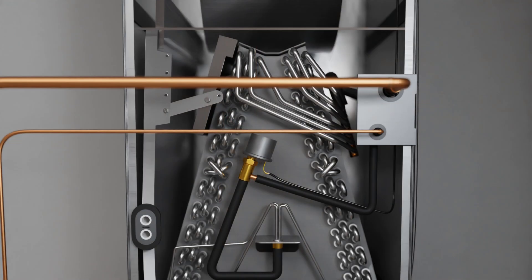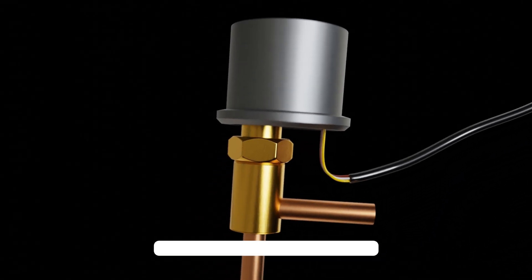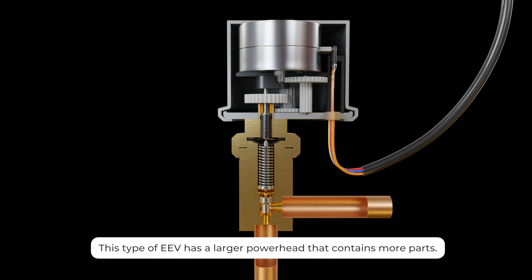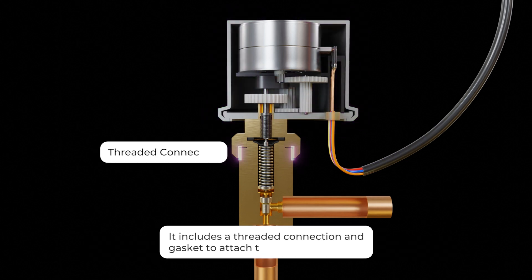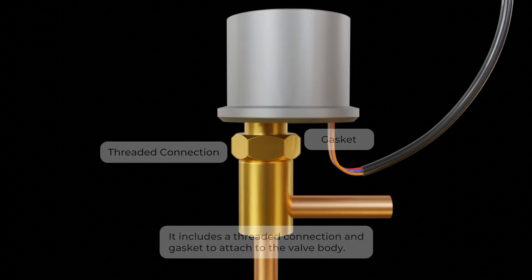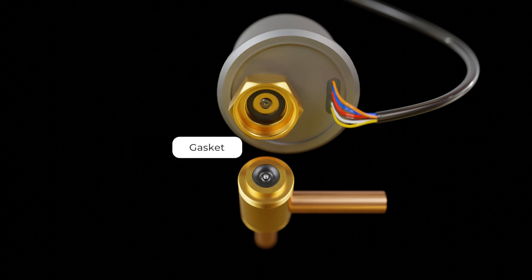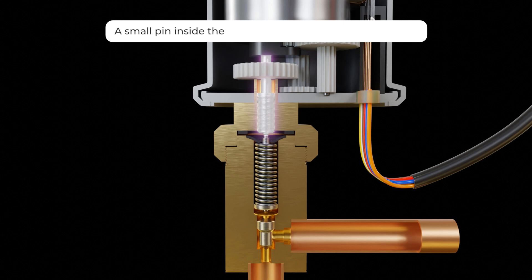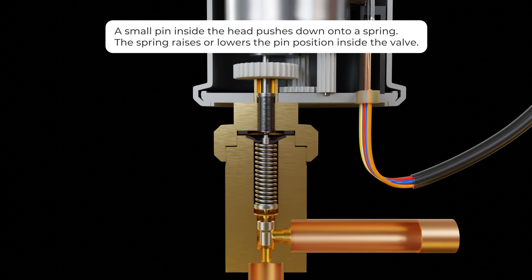The second type of EEV uses a direct drive motor instead of an indirect stepper motor. It's sometimes referred to as a gear driven expansion valve. This type of EEV has a larger power head that contains more parts including a threaded connection and gasket to attach the valve body. A solid connection allows a small pin inside the head to push down onto a spring which can raise or lower the pin position inside the valve.